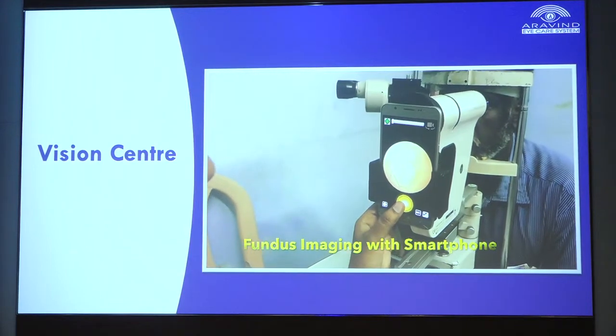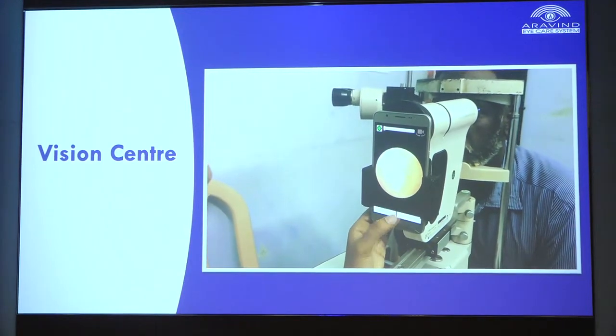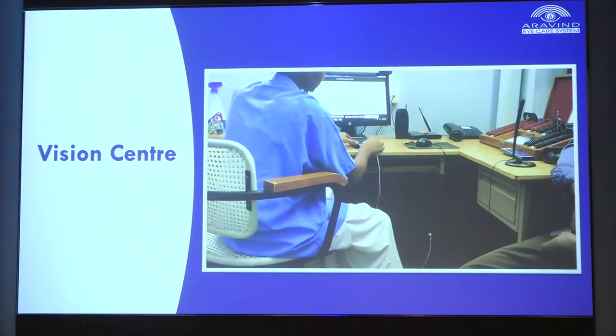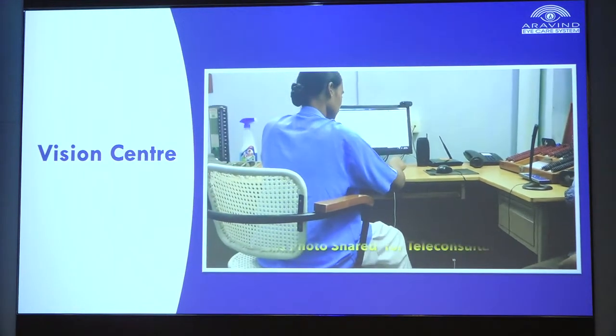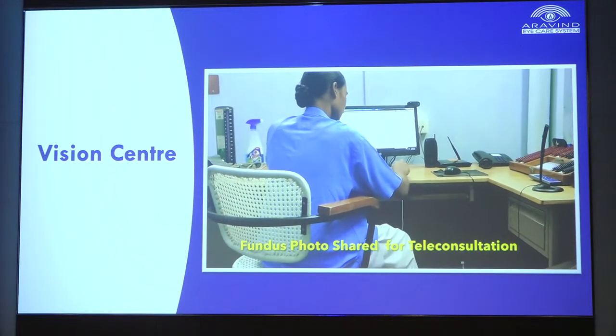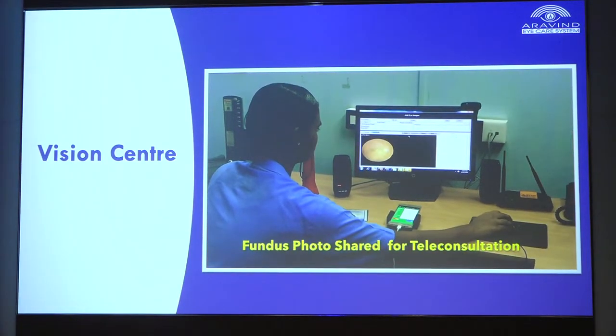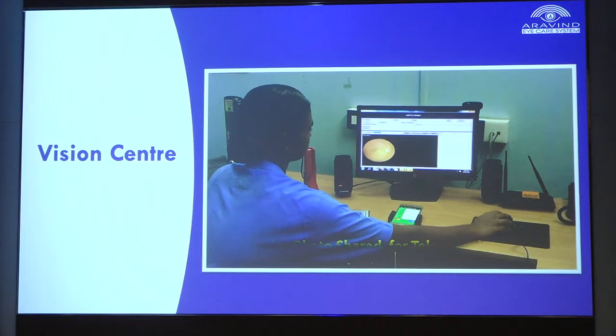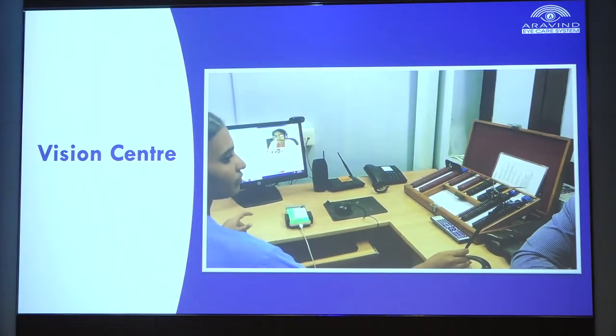Now we have attached the fundus on phone right in the slit lamp, so you don't have to move every time. They just have to move the slit lamp or the fundus on phone. And it is also attached to the EMR, so they don't have to remove the cable and upload the images. The images are automatically transferred into the fundus photo area of the EMR now.